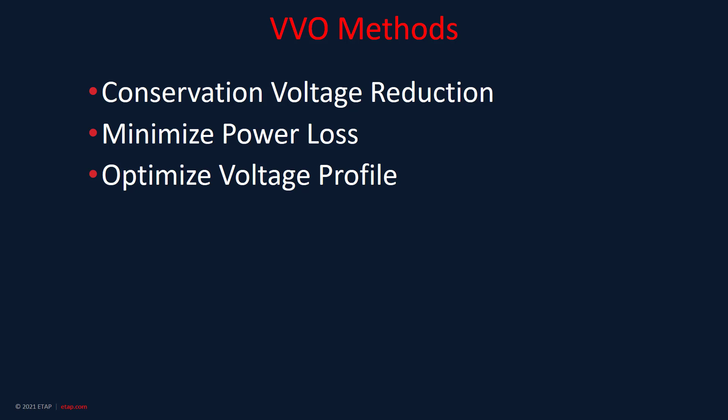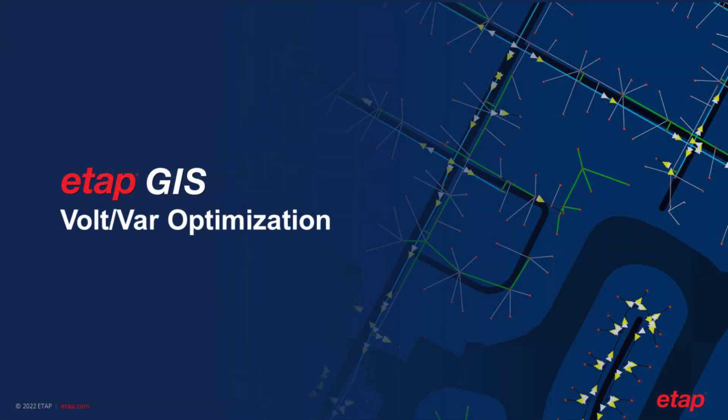The CVR factor of 1 means that a 1 percent reduction in voltage results in a 1 percent reduction in energy. Just keep voltage close to normal within voltage swings. A positive CVR factor is desired. Thank you everyone for attending this presentation.